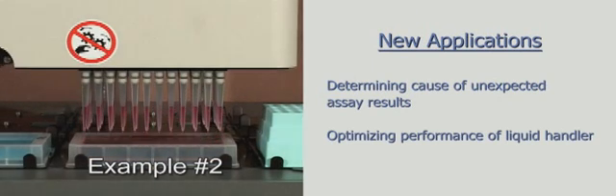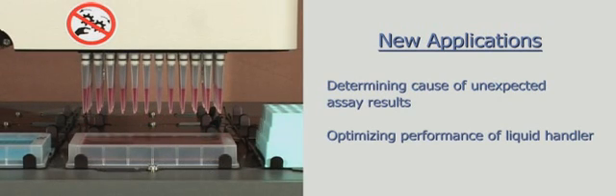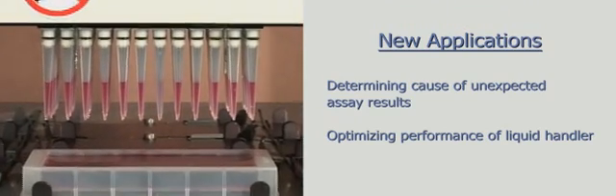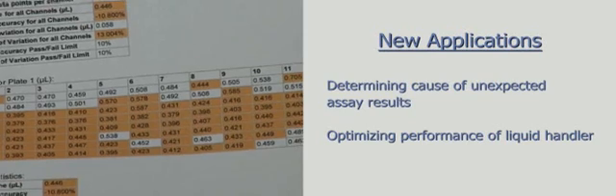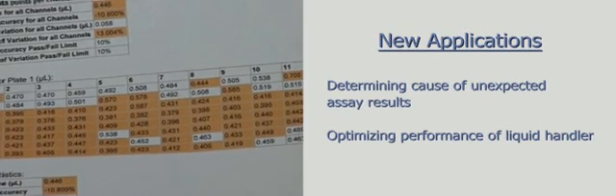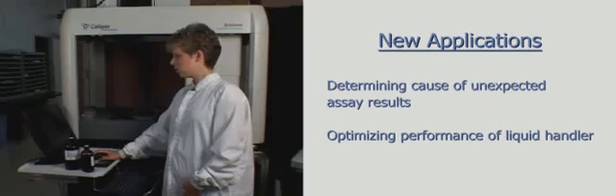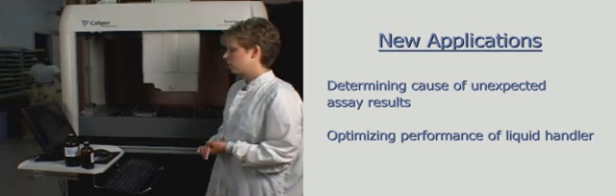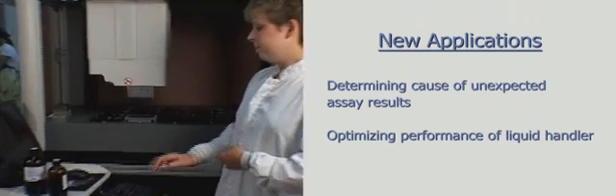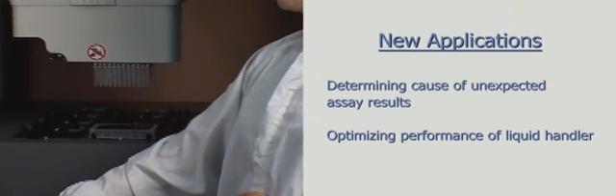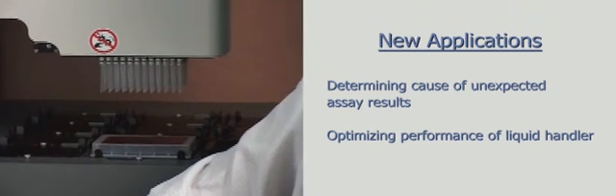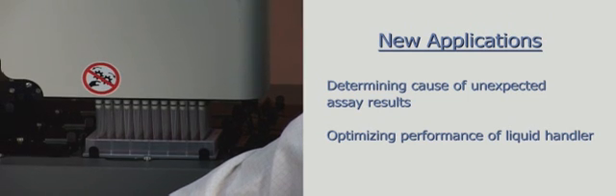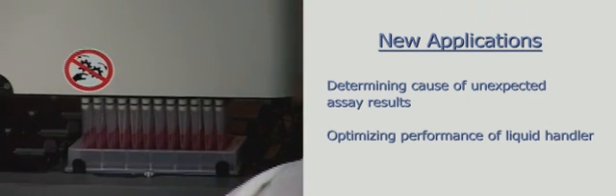You are setting up your liquid handling instrumentation for a new application, and your assay results do not correlate well with those obtained during development. Your troubleshooting points towards erratic or inaccurate liquid delivery. You need a means of determining quickly and accurately where the trouble lies. The MVS gives you the ability to do quick volume checks before and after a delivery. This quick diagnosis will provide you with maximum productivity and allow you to meet aggressive schedules with minimized waste.